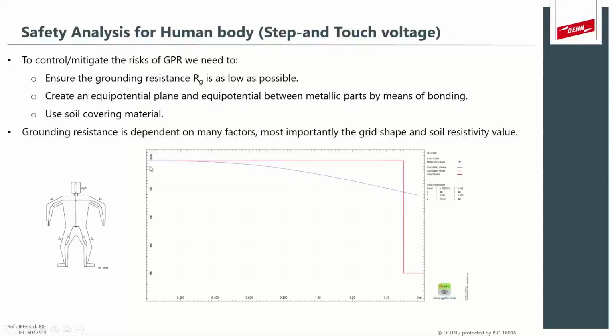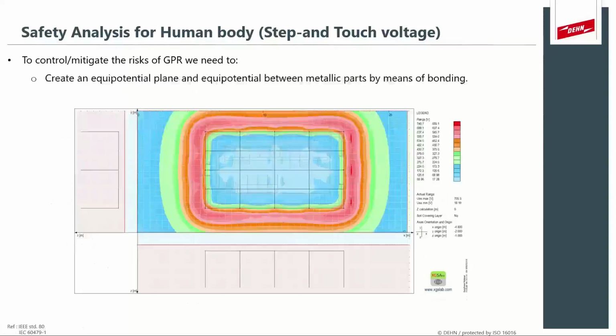And in this case, for our calculation today, we constructed a two-layer soil model, which has a soil resistivity on the upper level of 1,000 ohm meter for 1.5 meters deep, and then after that continues as 200 ohm meter down to the depths. In this case, we can see that the grid is safe against step potential.